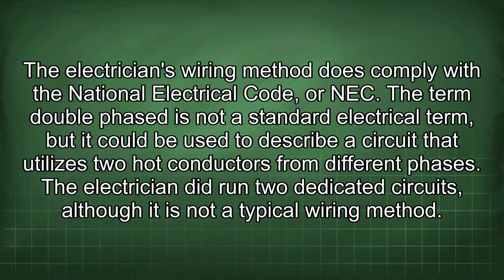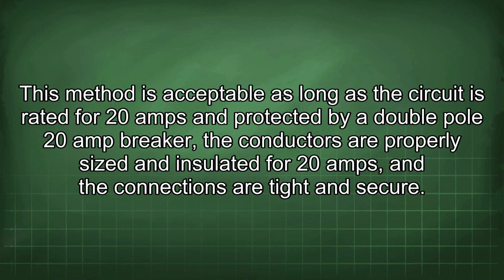The term double-phased is not a standard electrical term, but it could be used to describe a circuit that utilizes two hot conductors from different phases. The electrician did run two dedicated circuits, although it is not a typical wiring method. This method is acceptable as long as the circuit is rated for 20 amps and protected by a double-pole 20-amp breaker, the conductors are properly sized and insulated for 20 amps, and the connections are tight and secure.